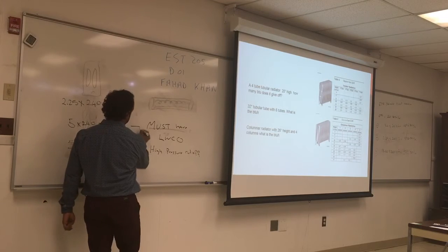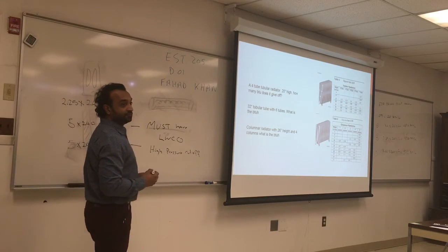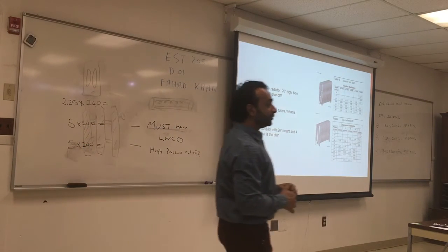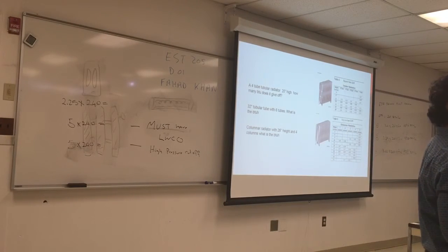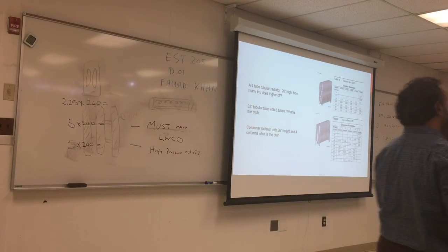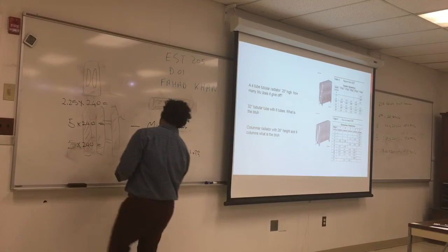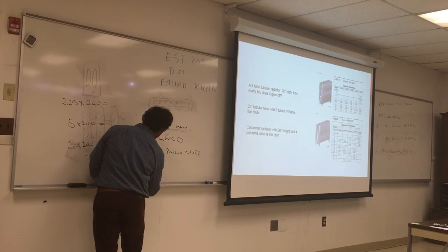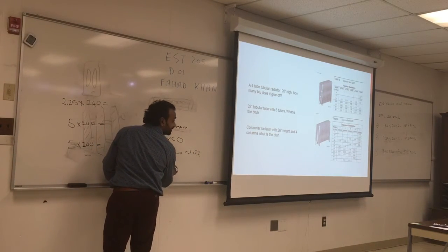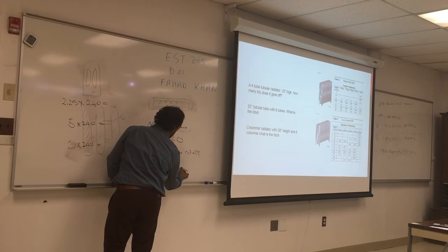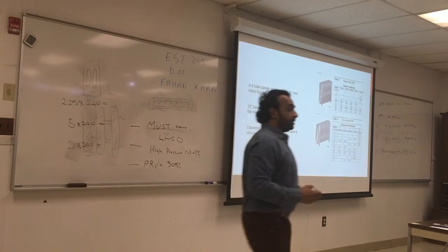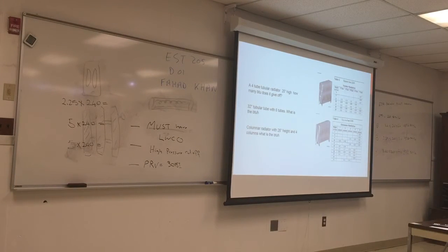These are two you must have. And what else are we going to have for steam? Relief valve, pressure relief valve. What is the pressure? Standard? 30 psi. It's very high for steam, but that's for safety. That's for when everything fails. Then it will pop.